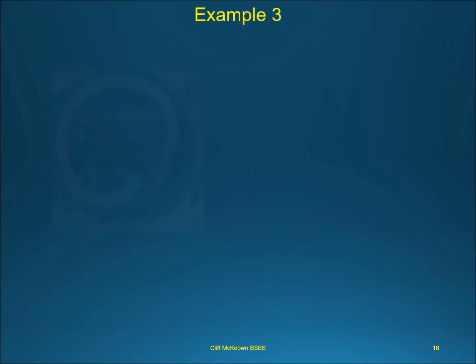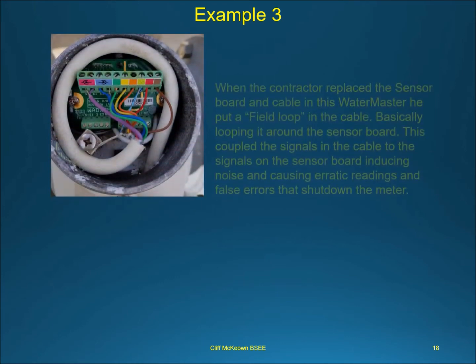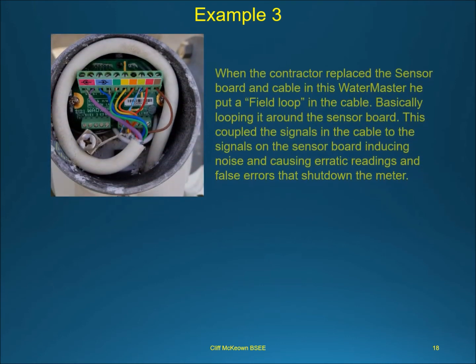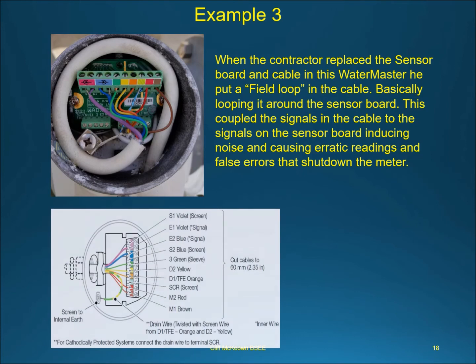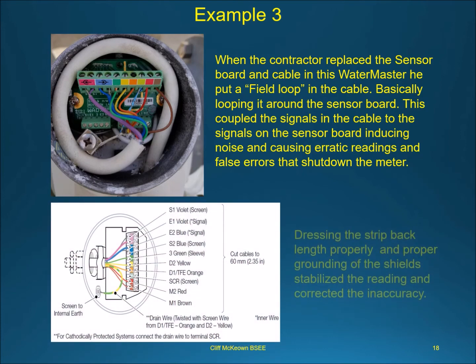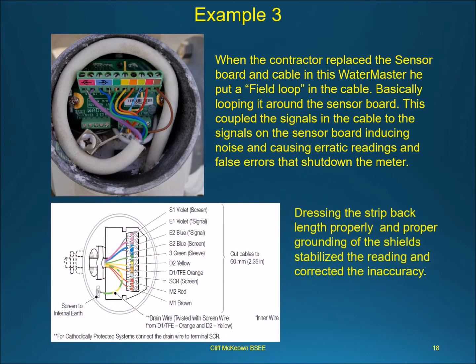When the contractor replaced the sensor board and cable in this Water Master, he put a field loop in the cable — basically looping it around the sensor board. This coupled the signals in the cable to the signals on the sensor board, inducing noise and causing erratic readings and false errors that shut down the meter. Dressing the strip-back length properly and proper grounding of the shield stabilized the reading and corrected the inaccuracy.